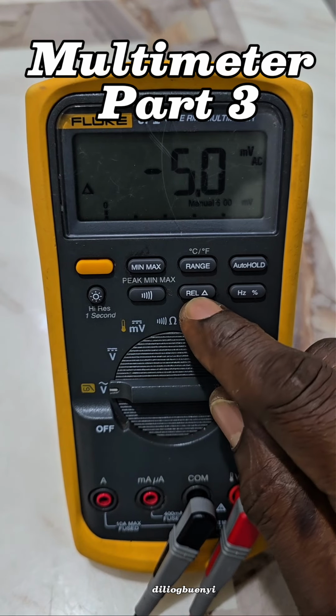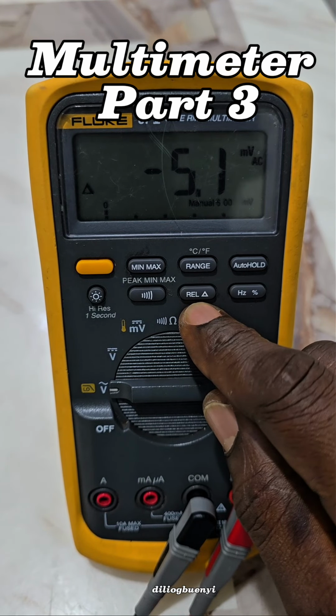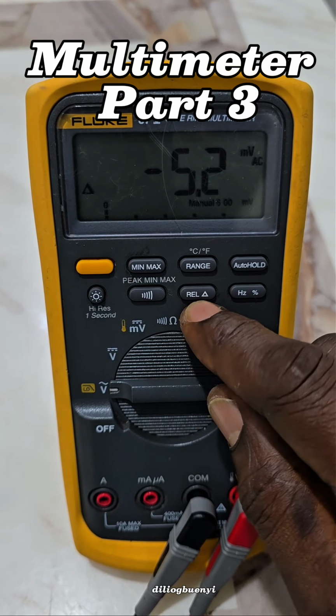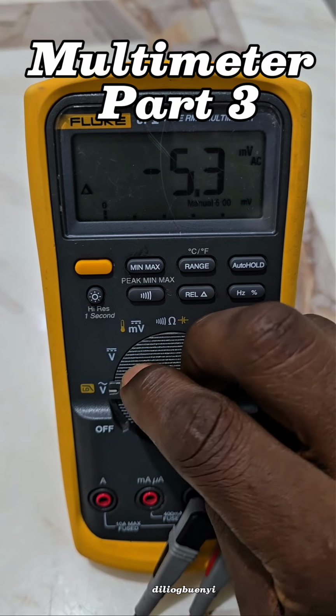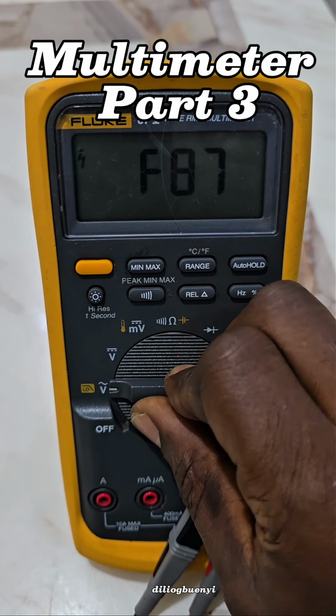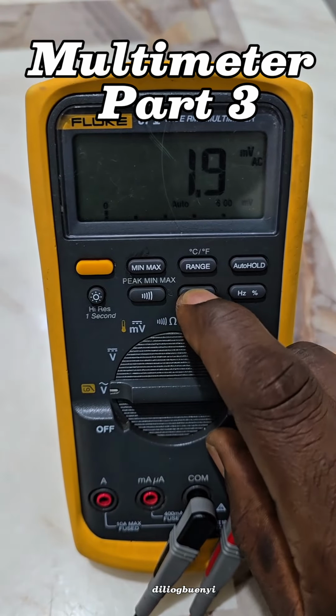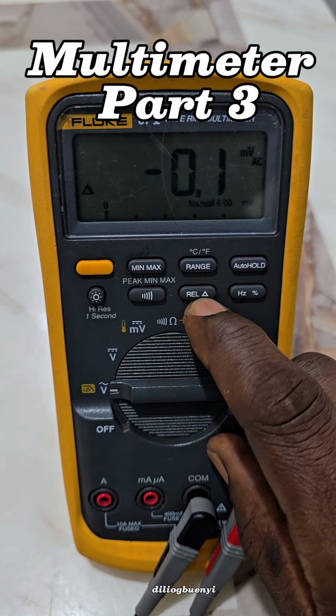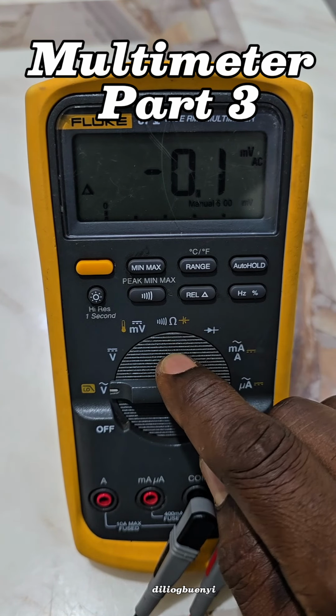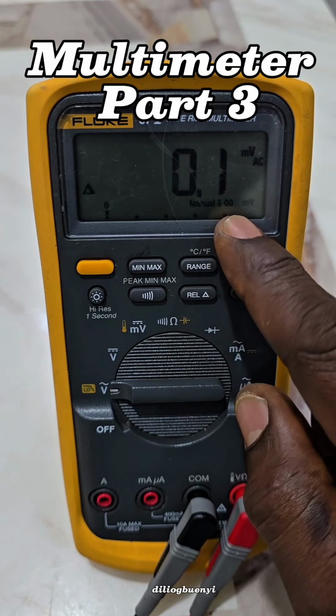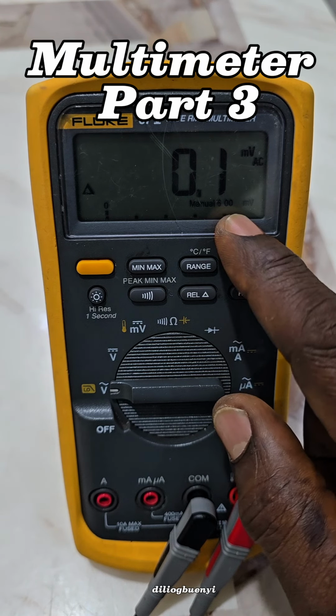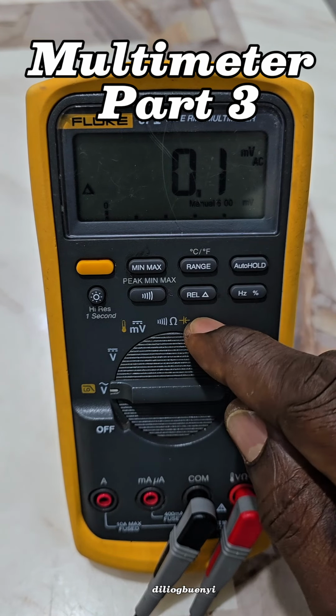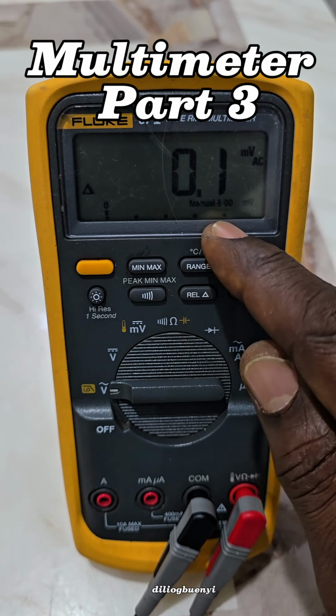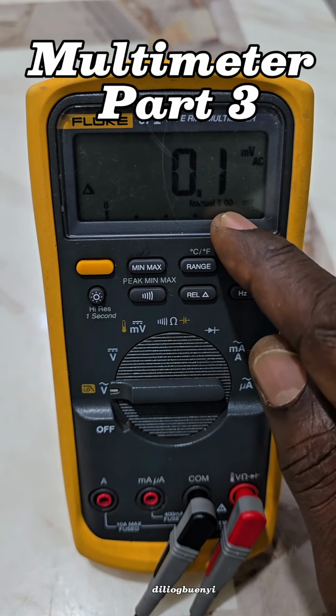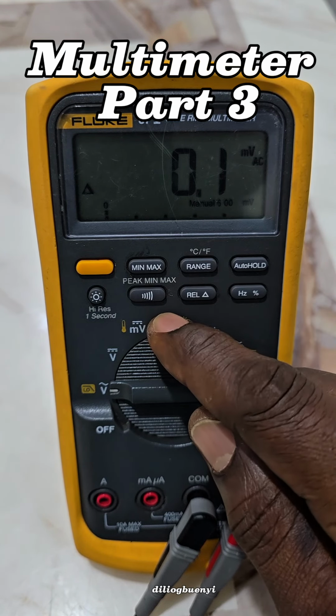So this one is the rel button or the relative button. What this one does is that when you are taking a measurement, for example, when you press this button, it records the existing reading but zeroes out this screen. Everything will be zero. So any other value you are going to measure is going to be the difference between the current reading and the stored reading.